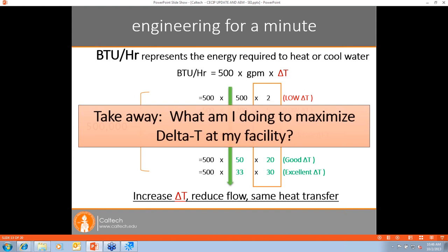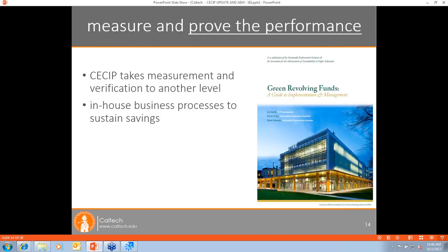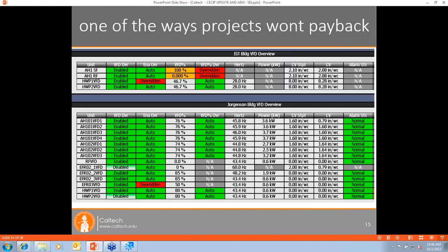So what's been done and where are we going? Let me just speed up a little bit here. We've picked up the low-hanging fruit. If I were looking at this in 2009, low-hanging fruit is things like changing light bulbs, dealing with motors on air handlers, things that are behind the scenes to most building occupants, maybe dealing with some free cooling. That's when we talk about economizers and doing work with damper control so we can ventilate buildings efficiently, not requiring mechanical cooling. We're going much more into deep retrofits now that rely on air side optimization, and specifically in laboratories. You can see the big numbers there, $8 a square foot down to $3.